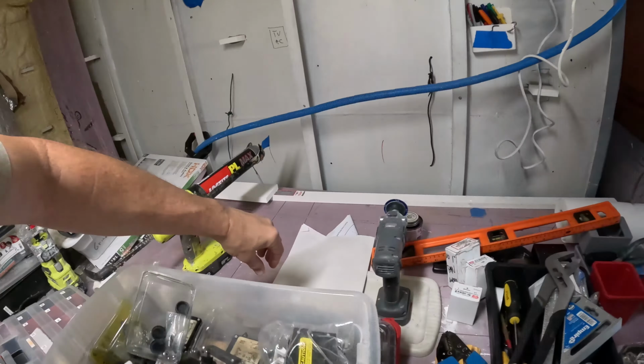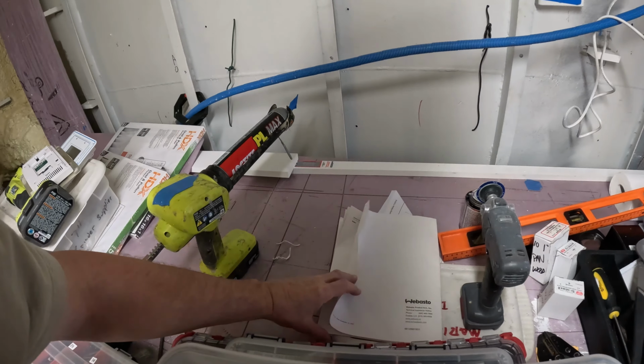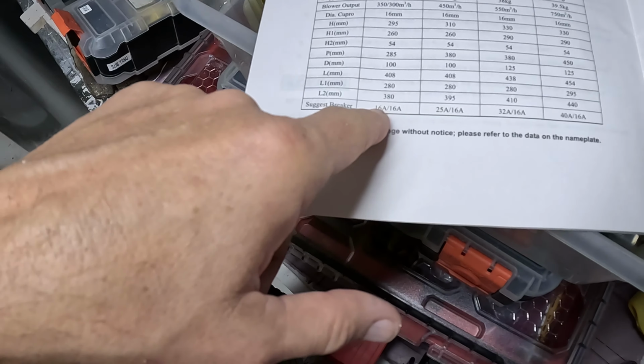With both ACs not cooling, the water has stopped, as you can see. I tracked down another 15 amp breaker, and I'm going with a 15 amp breaker since I only have one 10 amp breaker. The manual says to use a 16 amp breaker, for both 110 and 220, whereas on this one when you get to the 9000 it's 25, 16, 32, 16, and so on, probably not a true even split of power like other units.